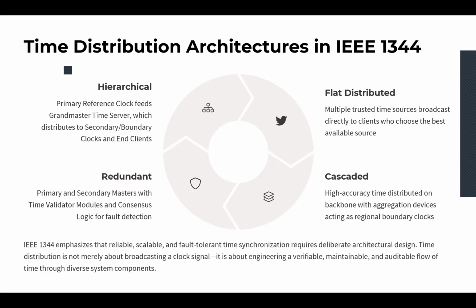A client must not accept time from multiple tiers. Obviously, we know what problems could be caused by that kind of incident. If there is time quality degradation, it must be tracked across handoff boundaries. In response, the standard provides a mechanism: it inserts time quality metadata at each hop, triggers alarms if cascade error exceeds any threshold, and provides isolation zones for maintenance or failure handling.